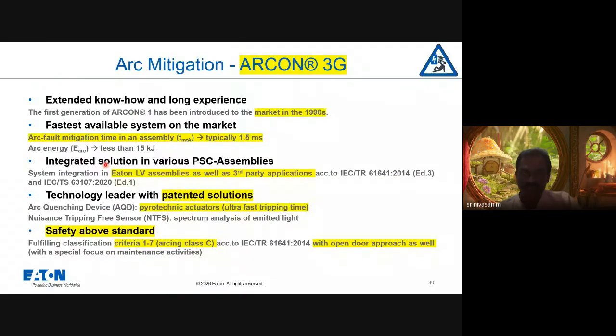So we will give the gist of the ARCON arc mitigation device. This device is not something new. It has been working globally for more than 35 years. It mitigates the arc in less than 1.5 to 2 milliseconds. This ARCON can be installed in third-party applications also, according to IEC 61641. It works on the design of a pyrotechnic actuator, exactly the same principle as how the airbag operates in a car. And this is safety above the standard. Apart from whatever IEC 61641 indicates, it also gives more protection and needs less maintenance time, so that we can put the switchboard back into service in less than 45 minutes.